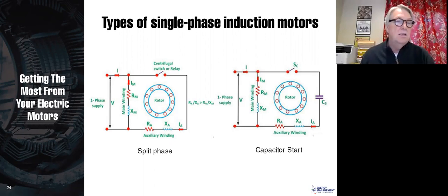As we said, on single phase motors, you don't get a rotating flux. You get just a flux, a magnet that goes up and down. So this creates a second magnet that allows that magnet to rotate, and it just helps us get the motor started. And once the motor is running, then we don't need that anymore. Then we open that up and get rid of that auxiliary winding, because with the auxiliary winding in there, we're going to end up with a motor that's much less efficient and lower power factor. And so we'll do that.